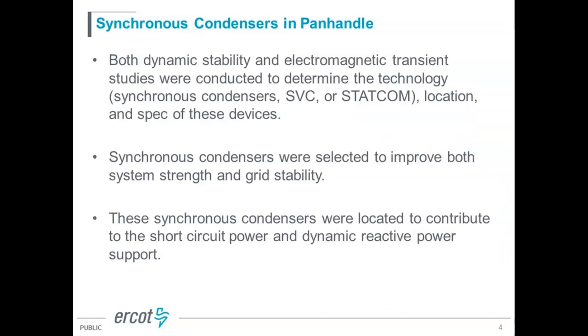Similar to what Dennis mentioned earlier, when we tried to identify system upgrades to improve the area, both typical dynamic stability analysis, such as PSSE or PSLF positive-sequence type analysis, and EMTP and PSCAD analysis were conducted for the Panhandle and nearby regions. This was to ensure we properly capture all the inverter-related weak grid issues, so that we can identify the results and determine the right technology.